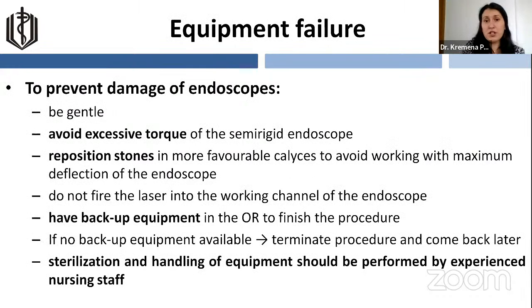Sometimes during the procedure, we may also experience failure of the equipment. To prevent damage of endoscopes, we should always be gentle and avoid excessive torque of the semi-rigid endoscope. We should try to reposition stones in more favorable calyces to avoid working with maximum deflection of the endoscope during flexible ureteroscopy. Also, do not fire the laser into the working channel of the endoscope to prevent injury to the instrument. It is advisable to have backup equipment in the OR to be able to finish the procedure. In some cases, when backup equipment is not available, consider terminating the procedure and coming back for a second procedure.